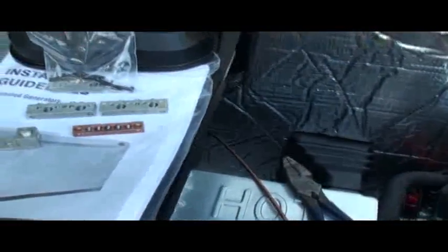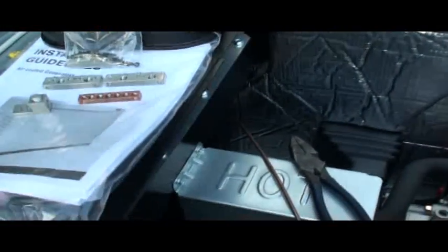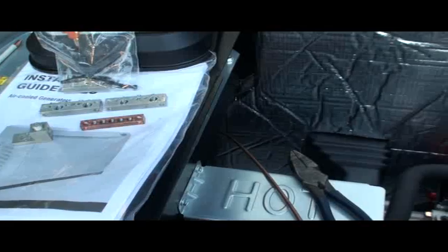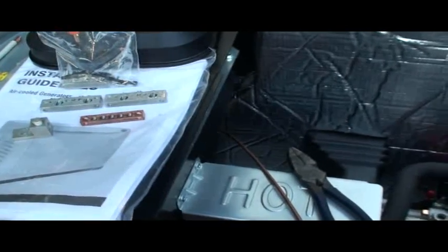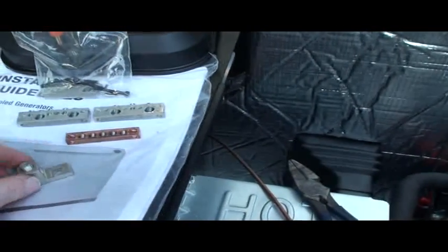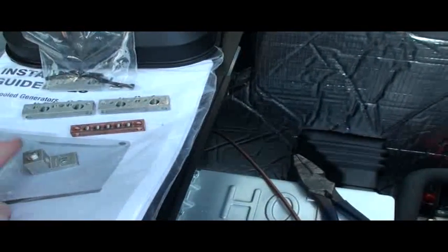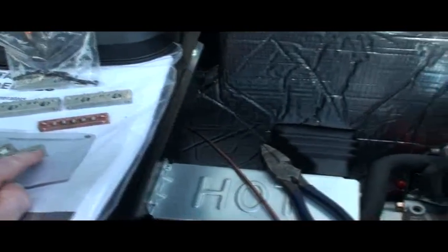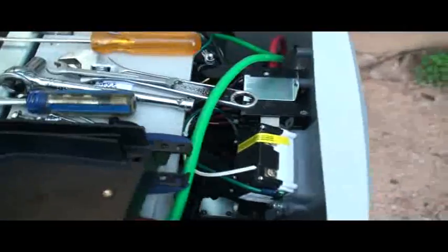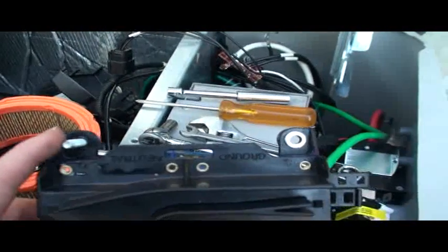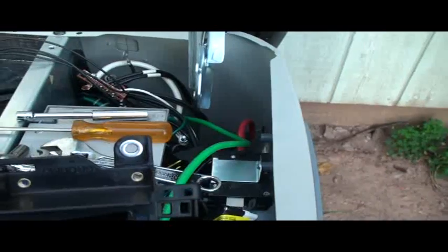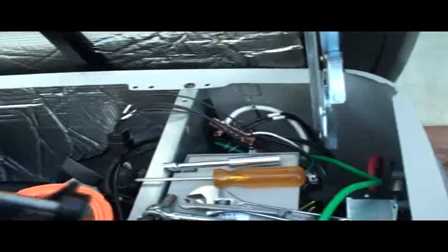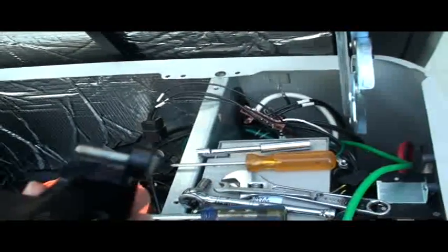So I called Generac, and Generac told me to use one of these lugs here to adapt it to a bolt stud. Because on this piece, as you'll see right here, they have a bolt stud here for the neutral and the one on the opposite side for the ground. But as you can see, these bolts are just in plastic.